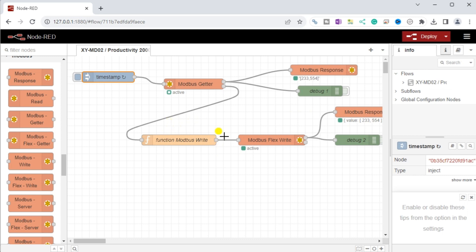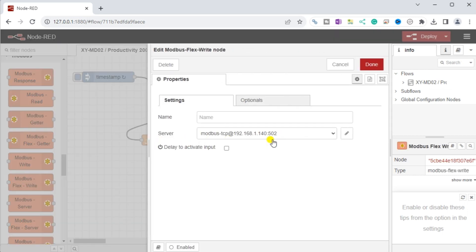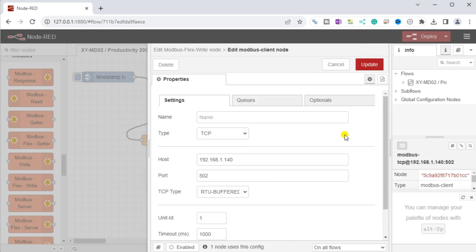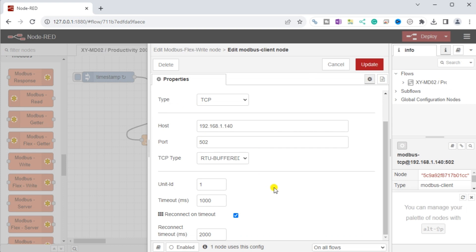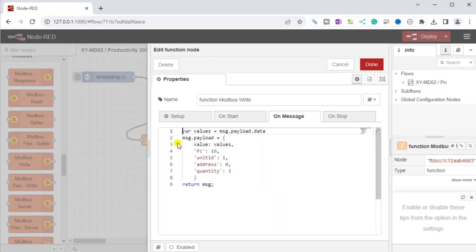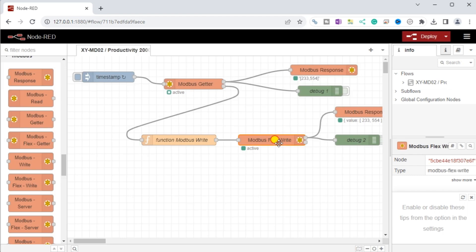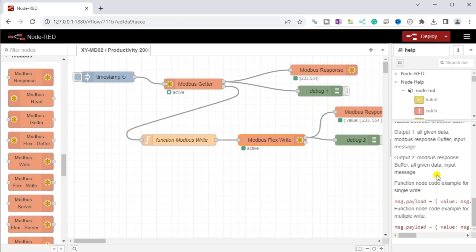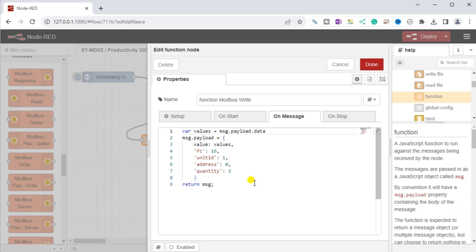A Modbus flexwrite node will be used to write the information from the XY-MD02 into the Productivity 2000 PLC. Once again we can set up the parameters for this node, using the P2000 PLC Ethernet Modbus server information to configure the Node-RED Modbus client node. Modbus flexwrite will use a function node to process the sensor values and prepare them for writing to the PLC. Once the values are processed, we can then pass them to the Modbus TCP node.